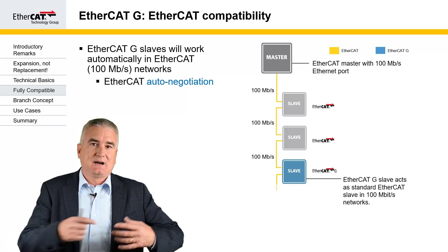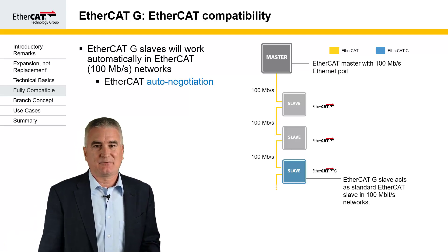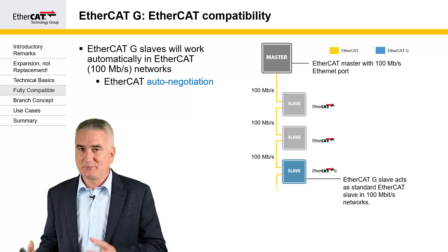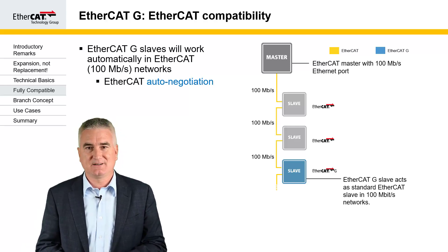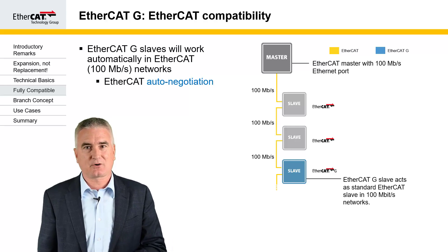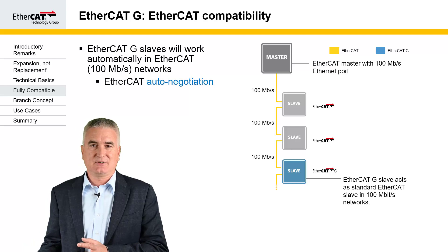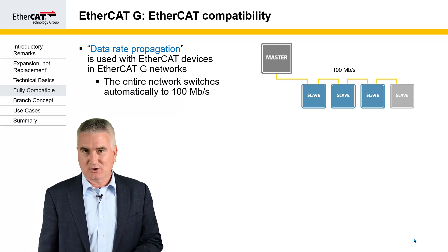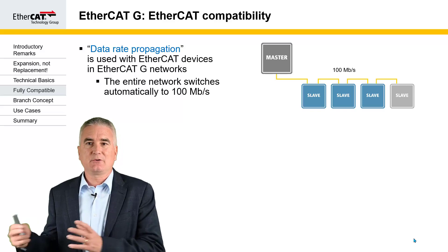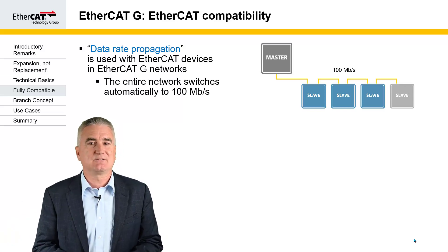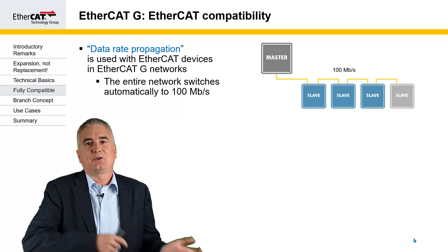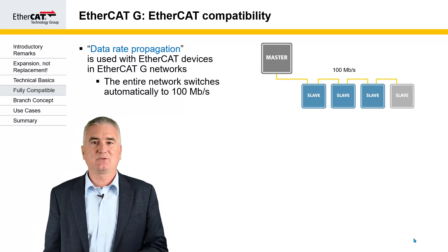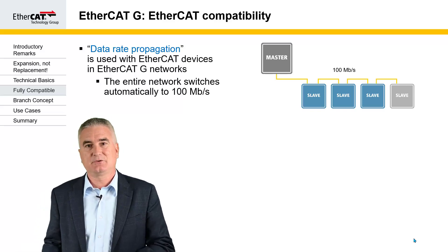It's very important that EtherCAT-G is fully downwards compatible to EtherCAT. Therefore, an EtherCAT-G slave introduced in a 100 megabit EtherCAT environment behaves exactly the same as a 100 megabit device. The auto-negotiation capability of the EtherCAT network ensures that, and the device is switched back to 100 megabit mode. In the other direction, this requires data rate propagation. If you introduce a 100 megabit device into a gigabit environment, the gigabit devices need to learn there is a 100 megabit device in the network. They do this with the data rate propagation functionality and then switch back to 100 megabit, making them fully compatible with the newly introduced device.